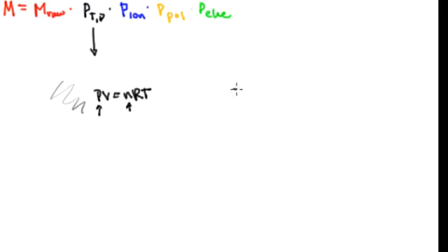If you have more atoms, you have more charge collected. So we'll correct by some factor for the pressure. So it's some standard, 760, that's millimeters of mercury. That's the standard pressure divided by the pressure. So if you have a higher pressure, the correction factor is going to go down. Now you're also going to have a correction factor for temperature. So let's say for a given pressure, if you decrease the temperature, the number of atoms would have to go up. So you have to correct for that.